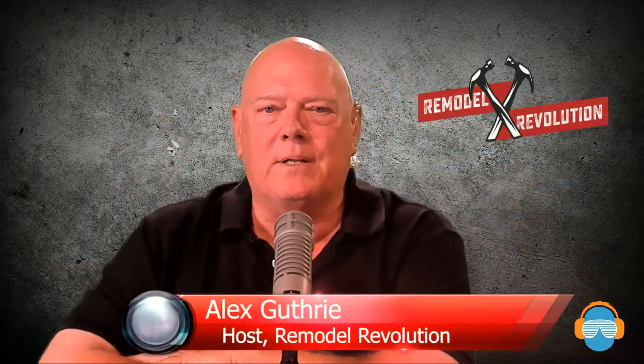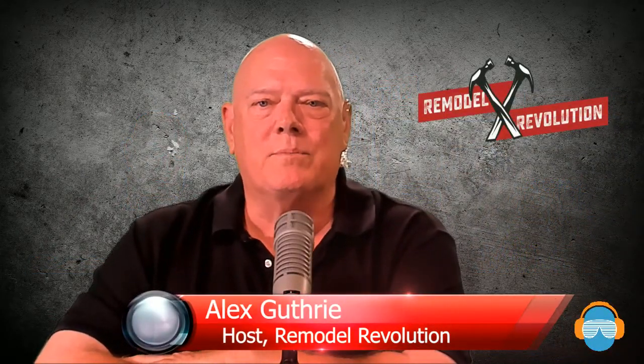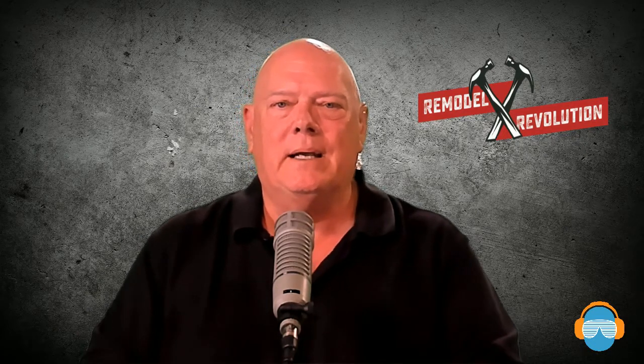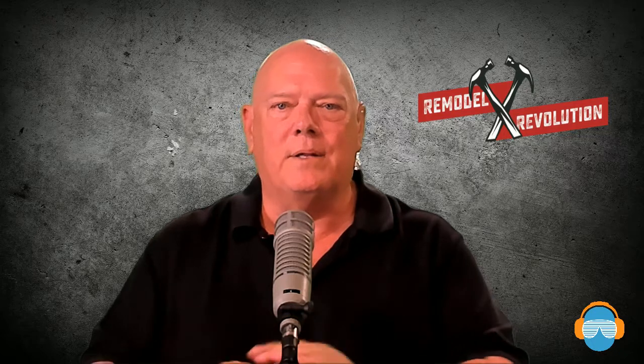Let's talk about metal duct - I look at houses every now and then that have it. I had one recently with a bunch of rusty areas, original duct from the 1950s, all metal, insulated from the outside with what looks like foil wrapping over insulation. When we pulled some of that back, we found rusty areas in the duct. My immediate reaction was that it had to be replaced, but the air conditioning contractor the homeowner talked to didn't agree. It sounds like AeroSeal could help with situations like that.